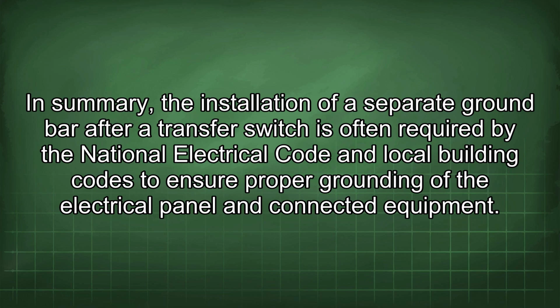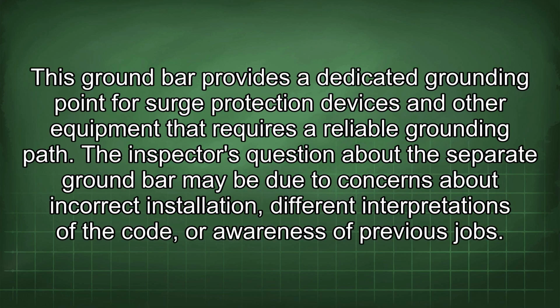In summary, the installation of a separate ground bar after a transfer switch is often required by the National Electrical Code and local building codes to ensure proper grounding of the electrical panel and connected equipment. This ground bar provides a dedicated grounding point for surge protection devices and other equipment that requires a reliable grounding path. The inspector's question about the separate ground bar may be due to concerns about incorrect installation, different interpretations of the code, or awareness of previous jobs.